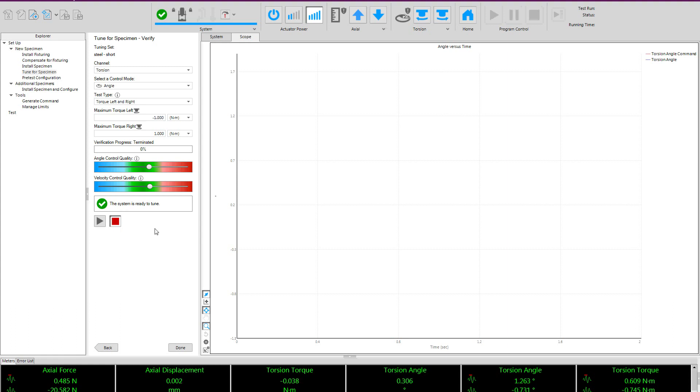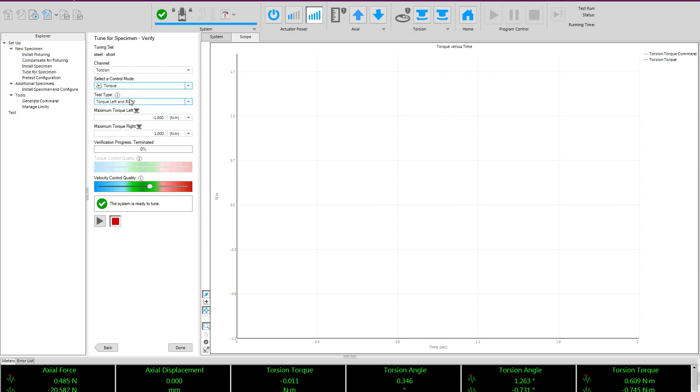You can see the options are very similar, but we have an additional option where we choose which control mode we are actually going to tune. The previous step was performed in the always stable control mode, and now we are going to verify the values actually created for the tuned control mode.